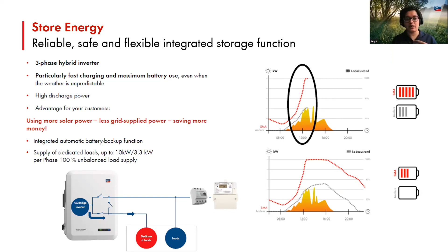With the three phase hybrid inverter, you have two MPPT trackers. The inverter up to 10 kilowatt has 3 strings. Other inverters have 2 strings that you can connect. With high current, you can overload up to 150%, and you can have other PV inverters installed in parallel in combination with this hybrid inverter. So if you have an already existing PV system, you can add on this inverter along with the batteries, and you can increase your system capacity.